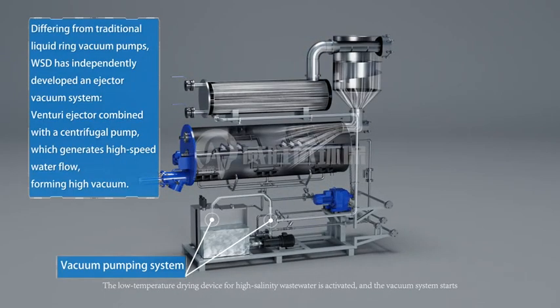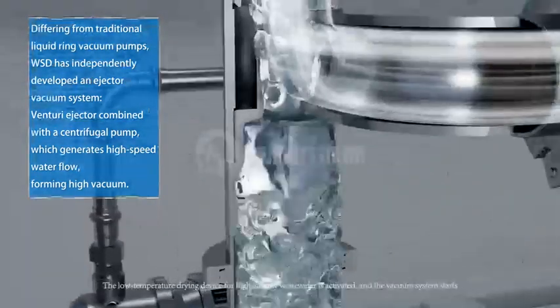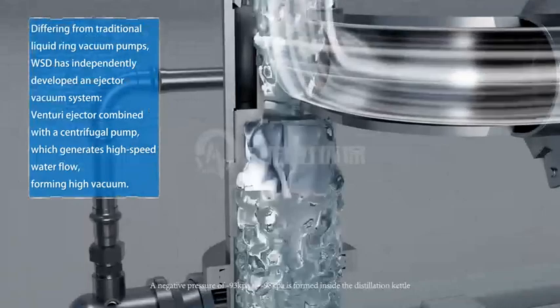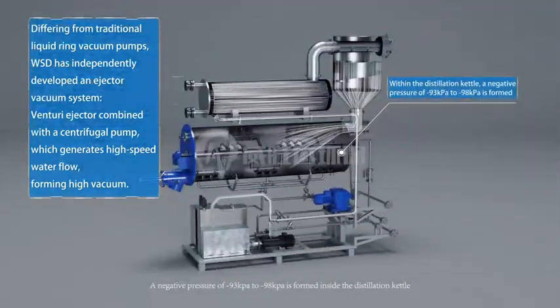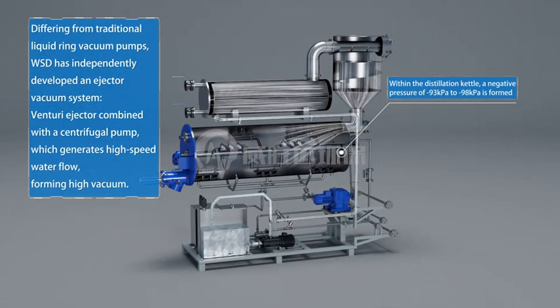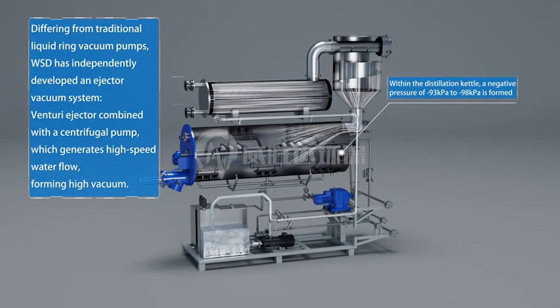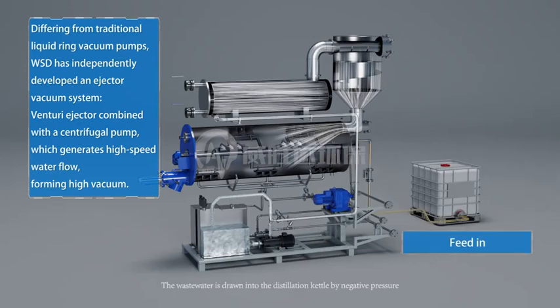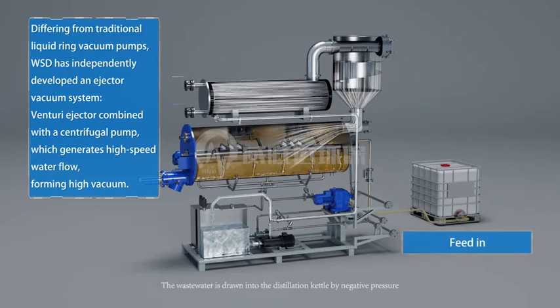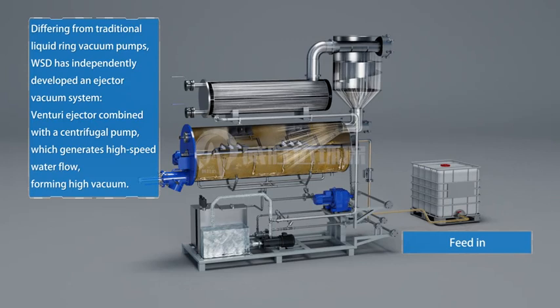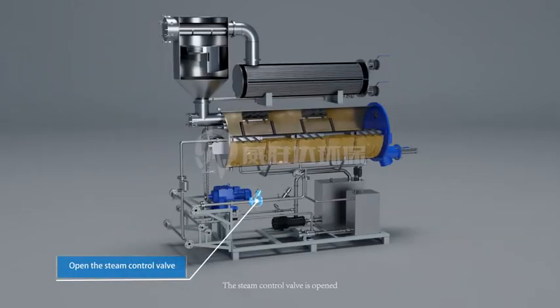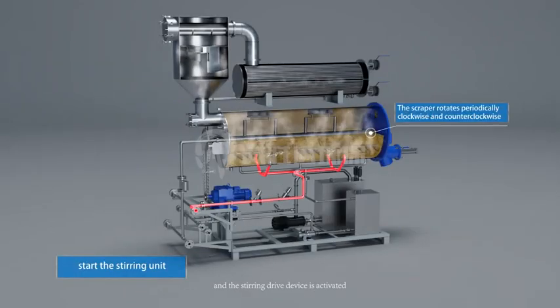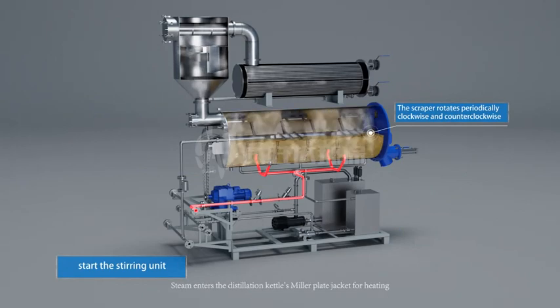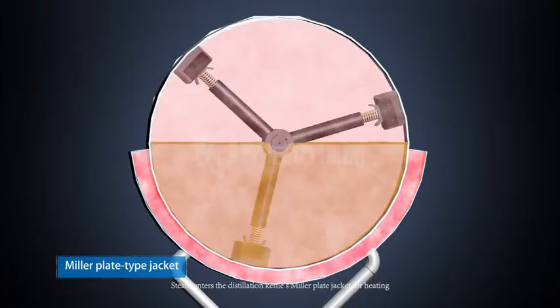The low-temperature drying device for high-salinity wastewater is activated and the vacuum system starts. A negative pressure of negative 93 kPa to negative 98 kPa is formed inside the distillation kettle. The water is drawn into the distillation kettle by negative pressure. The steam control valve is opened and the stirring drive device is activated. Steam enters the distillation kettle's Miller plate jacket for heating.